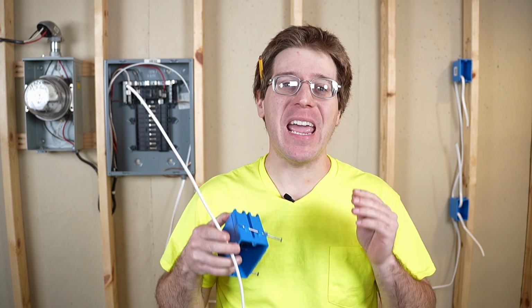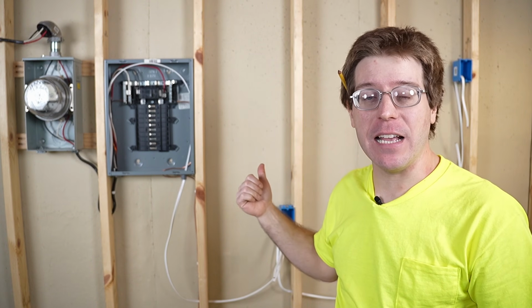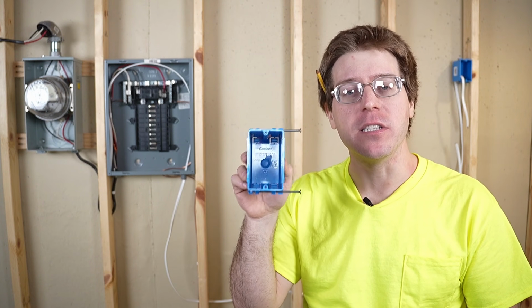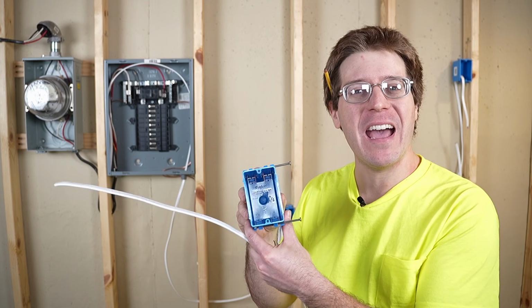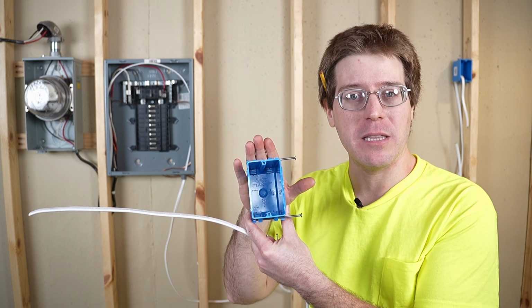In the video I did about installing a single receptacle, I mentioned that Romex, or NM, needs to be strapped within 12 inches of entering the box, and that is true. However, I made a slight omission in that last video. When Romex, or NM, enters a non-metallic box that does not have a strap built within the box, we actually have to strap within 8 inches of the box. So we're gonna actually have to make sure we strap within 8 inches of these non-metallic boxes, just because these non-metallic boxes don't have any sort of connector built within the box.